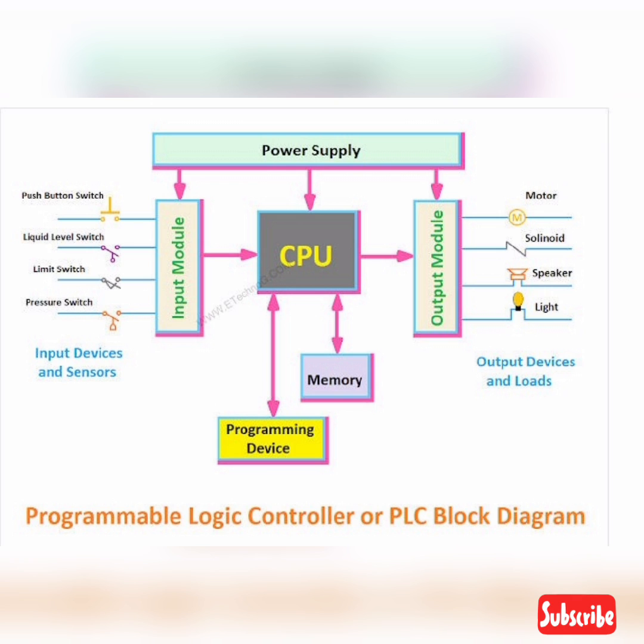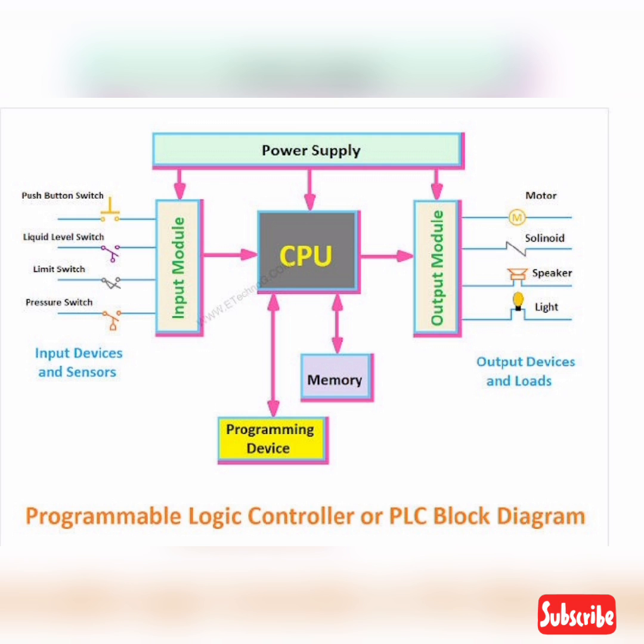Input and Output Module: the CPU or microprocessor can work with 5 volts DC supply and it can deliver very small output current. But the input devices or sensors may not work with the same voltage — that is, 5 volts DC. So to interface real-world input devices and sensors with the microprocessor, the input module is used. The input module always gives a 5 volts DC input signal to the CPU.